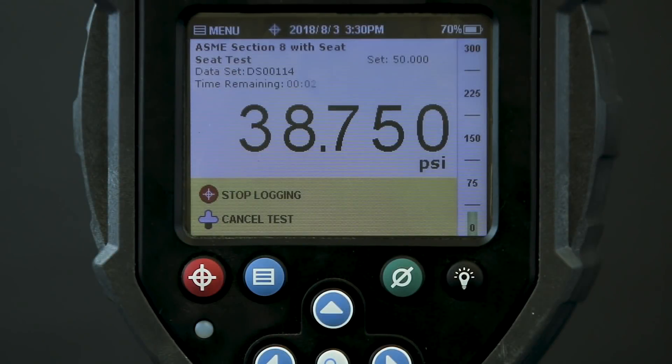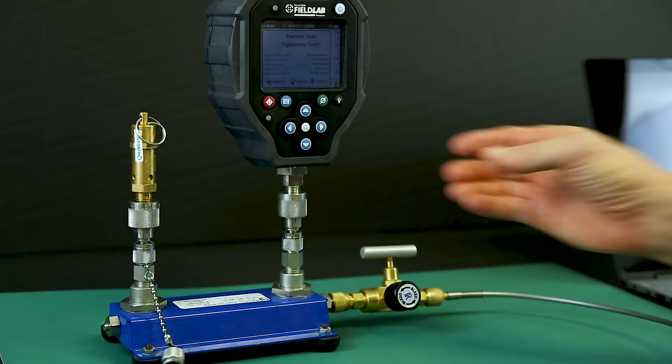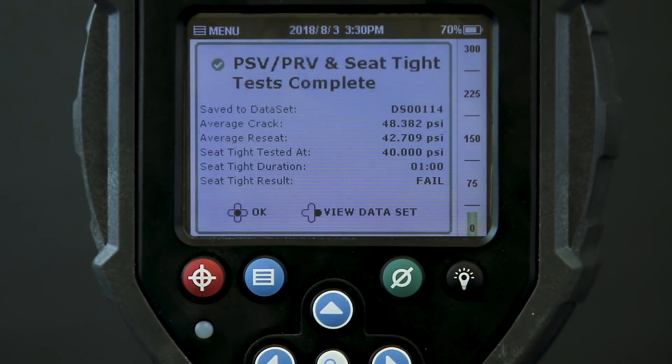After a minute has passed, the test shows there has been a change in pressure and we can see how much it has dropped. This information combined with my bubble test indicates that the valve was leaking, so I'll mark this test as failed. If the soap bubble test did not show a leak but I still had a pressure drop, I would do the same tests on the manifold and fittings to make sure the leak wasn't happening somewhere else. Now my test is complete and all the data for this series of tests is stored in the FieldLab.